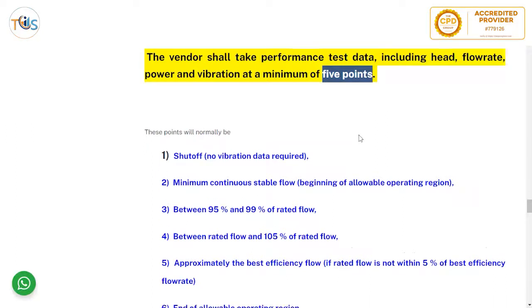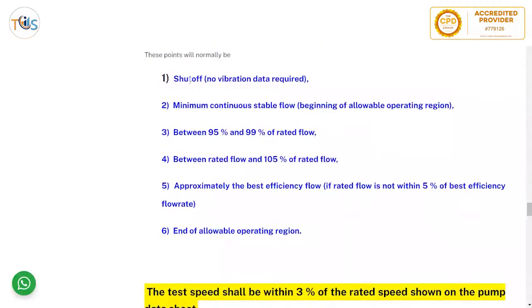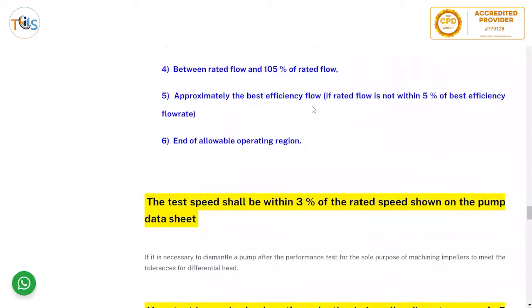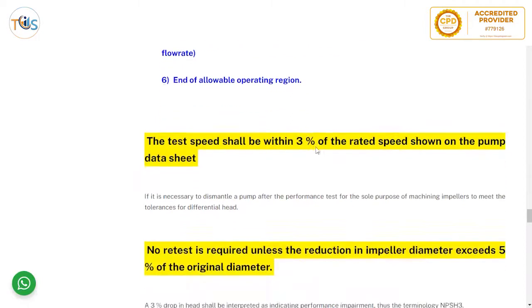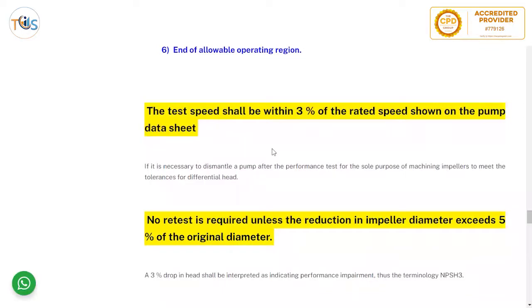The five test points shall normally be: the shutoff point (no vibration data required here); minimum continuous stable flow; beginning of the allowable operating region; between 95–99 percent of rated flow; between rated flow and 105 percent; and approximately the best efficiency flow rate if rated flow is not within 5 percent of it; and at the end of the allowable operating region. The test speed shall be within plus or minus 3 percent of the rated speed shown on the pump.